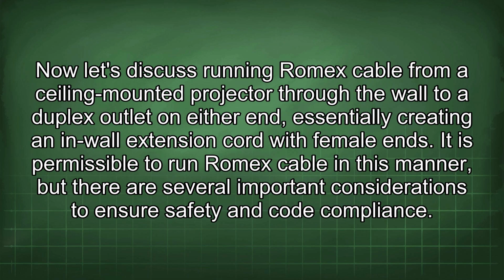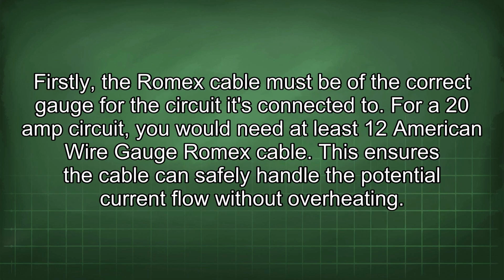Now let's discuss running Romex cable from a ceiling-mounted projector through the wall to a duplex outlet on either end, essentially creating an in-wall extension cord with female ends. It is permissible to run Romex cable in this manner, but there are several important considerations to ensure safety and code compliance. Firstly, the Romex cable must be of the correct gauge for the circuit it is connected to. For a 20 amp circuit, you would need at least 12 American wire gauge Romex cable. This ensures the cable can safely handle the potential current flow without overheating.